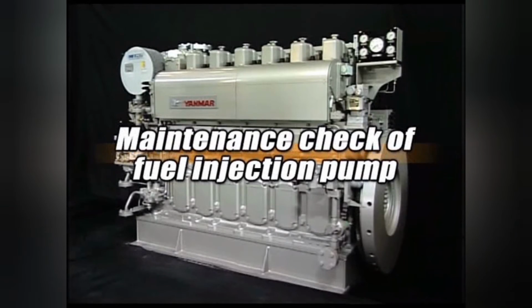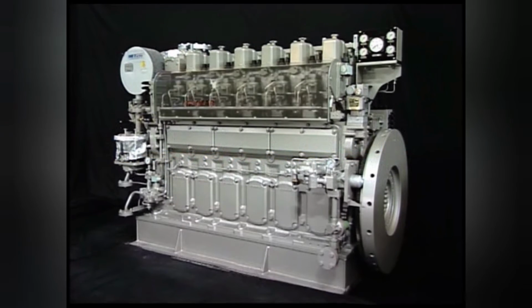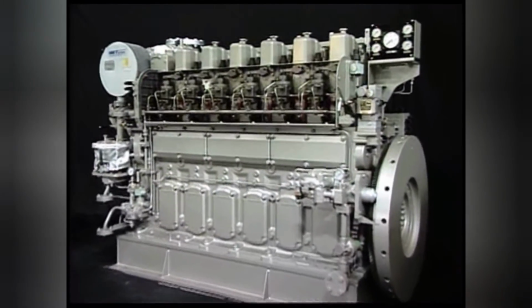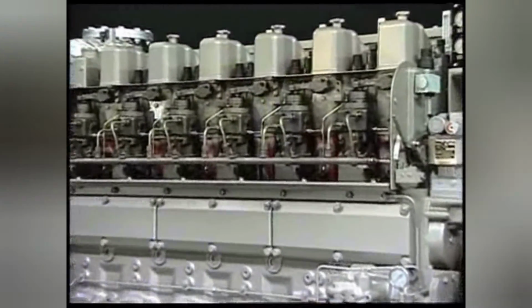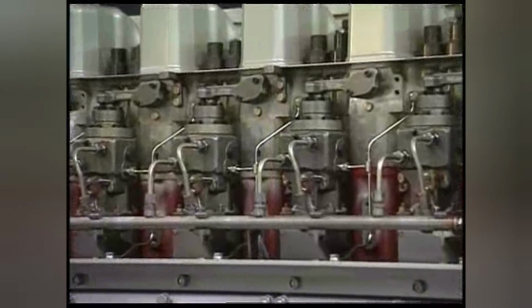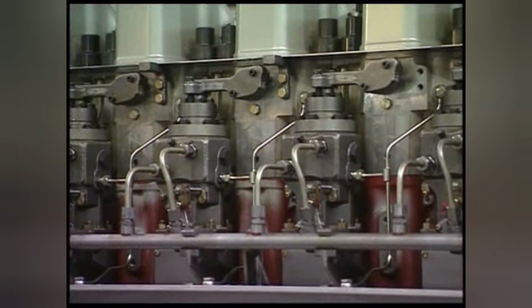This is the explanation for daily maintenance check of fuel injection pump. Check the rack graduation and the oiling quantity of pinion at every 300 to 500 hour intervals. I will explain the procedure.